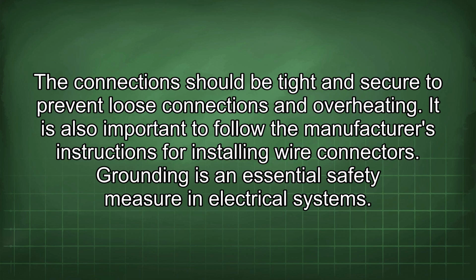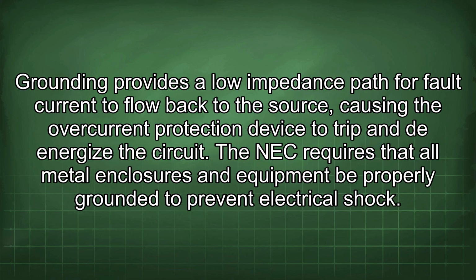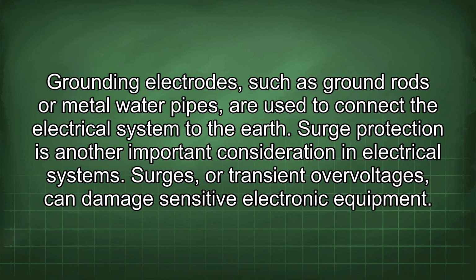Grounding is an essential safety measure in electrical systems. Grounding provides a low impedance path for fault current to flow back to the source, causing the overcurrent protection device to trip and de-energize the circuits. The NEC requires that all metal enclosures and equipment be properly grounded to prevent electrical shock. Grounding electrodes, such as ground rods or metal water pipes, are used to connect the electrical system to the earth.